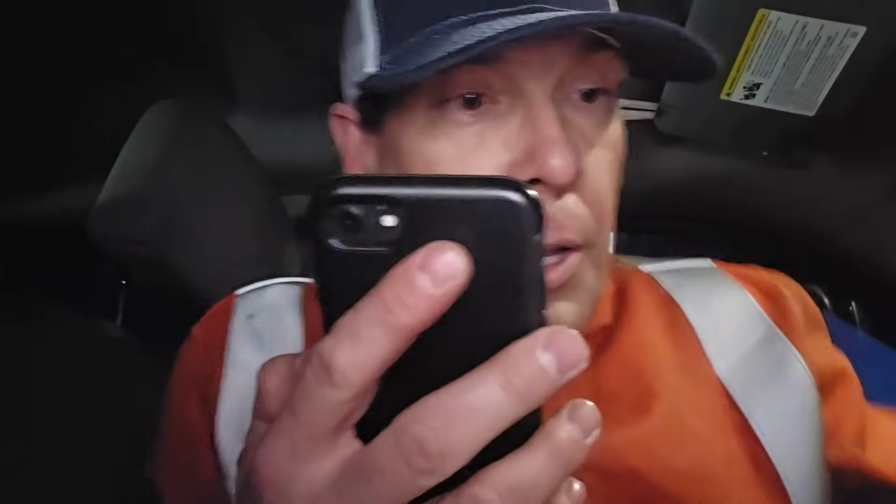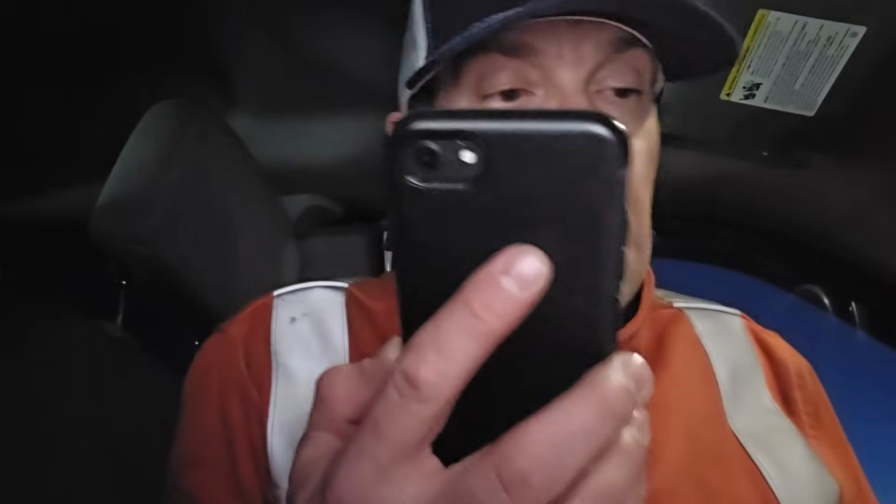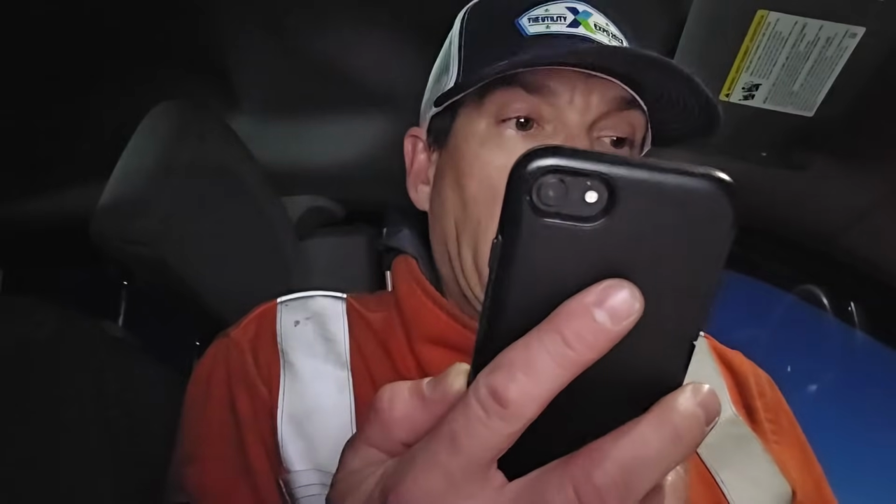Hey, Jeff, it's Aaron here. How you doing? Good, man. Yourself? Good, good. I've got a permit out, 160542, ready to surrender. All right, I got her up here, man. You can go ahead whenever you're ready. All right, so we've completed our work permit 160542 between protection points 8209 SO46 and 8209 SO10. All work has been completed as planned, temporary grounds and bonds have been removed, and men are clear and instructed to remain clear. 10-4, Aaron, so understand, surrendering your work permit 160542 between protection points 8209 SO46 and 8209 SO10, and all work was completed as planned. All personnel are clear and instructed to remain clear, and all temporary bonds and grounds have been removed there. 10-4, that is correct.